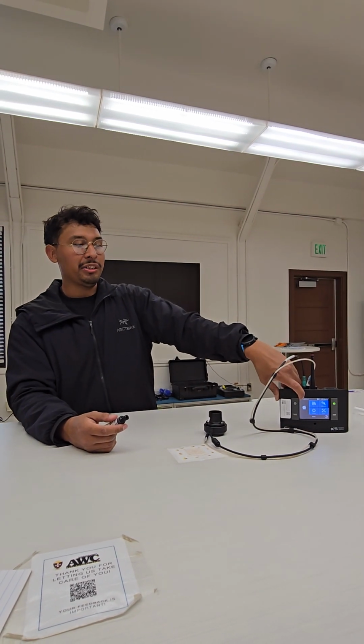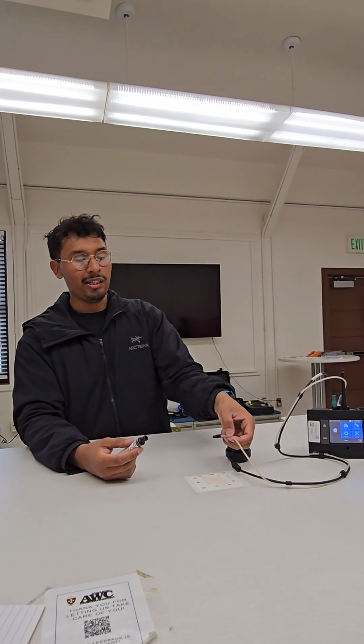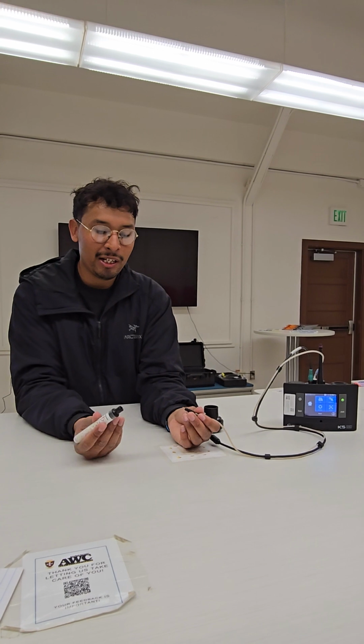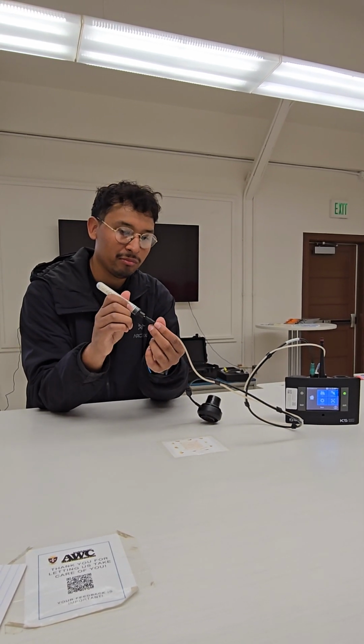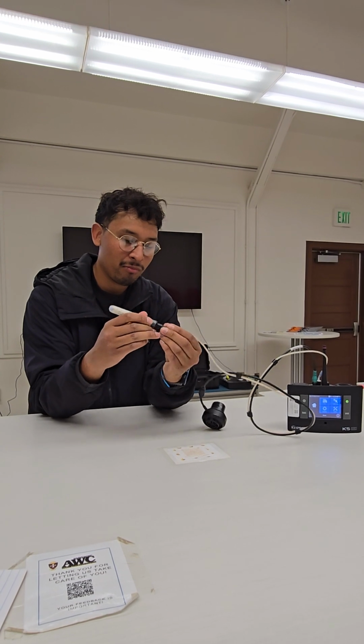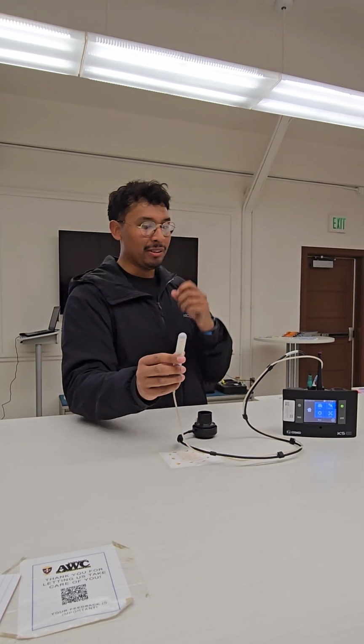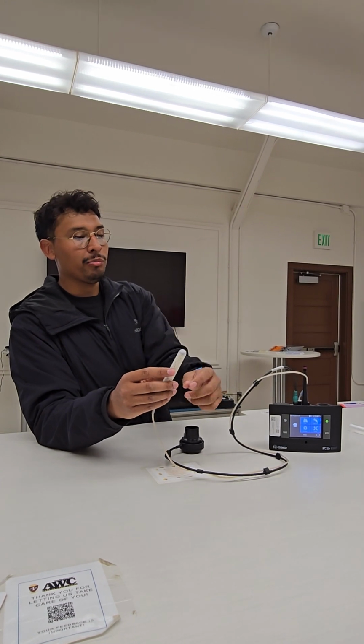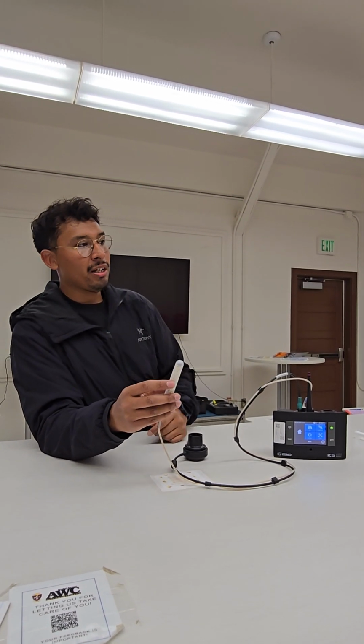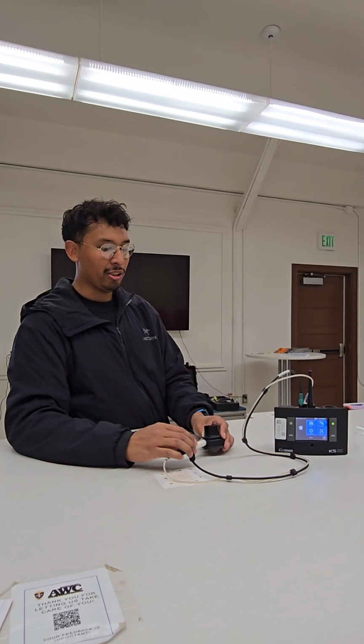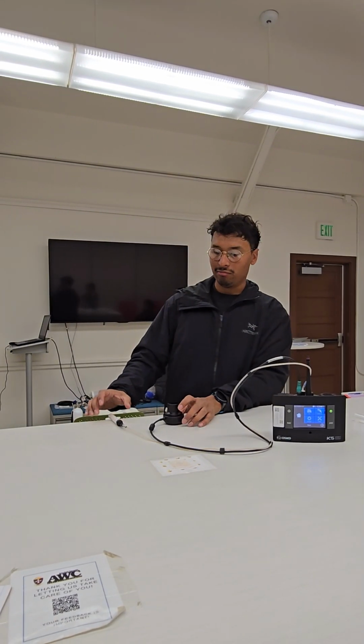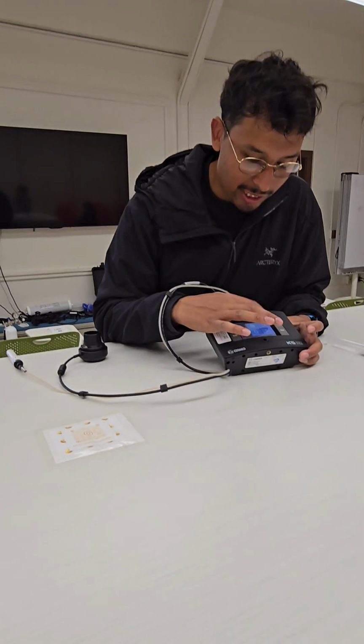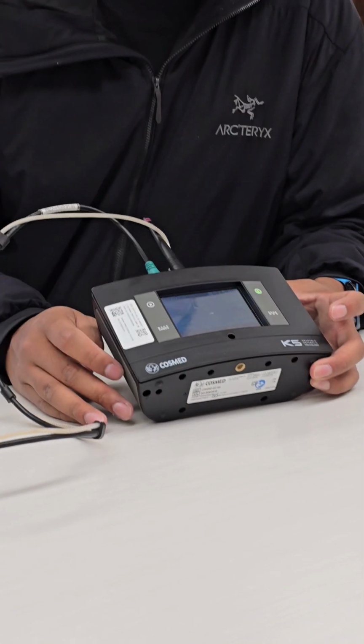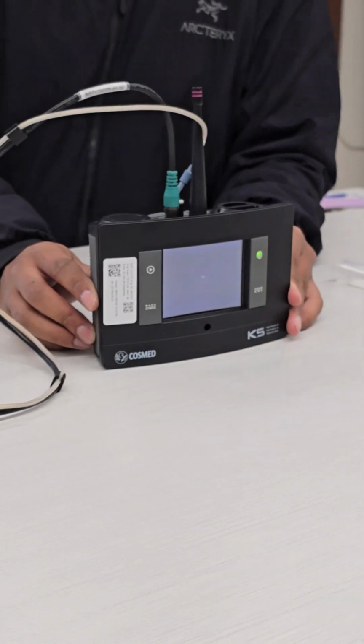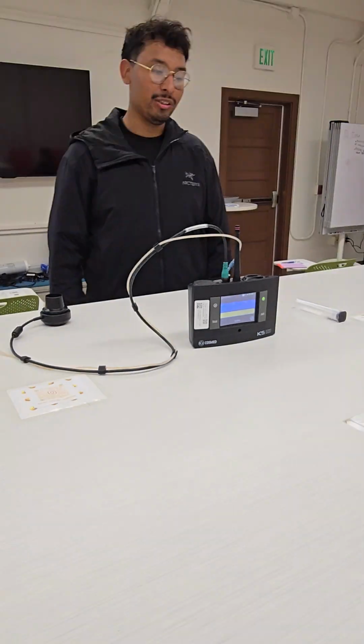Before you go into the calibration and then CO2 scrubber, go ahead and plug it in, because as soon as you press on the tile, it'll go into the calibration. The sampling line will go onto the top port here, so just place it in there. Basically what happens, like I said, is air is being moved up the tube, so try not to breathe on this end, and try not to have it obstructed in any way. So just let it hang. So calibration and scrubber. And we're probably gonna fail because of the sampling line, but we'll see.